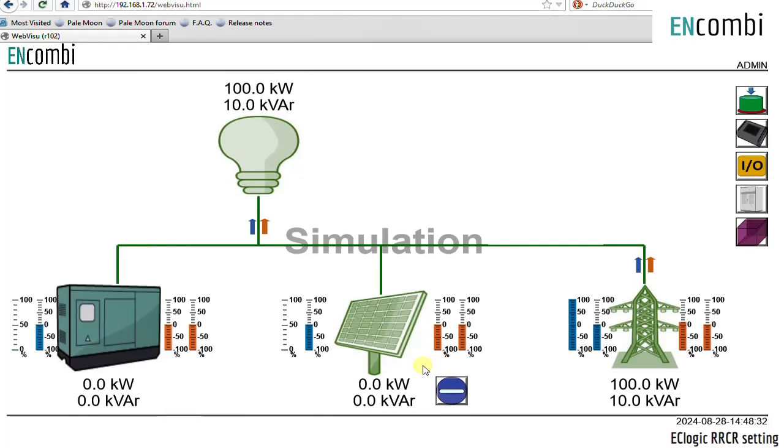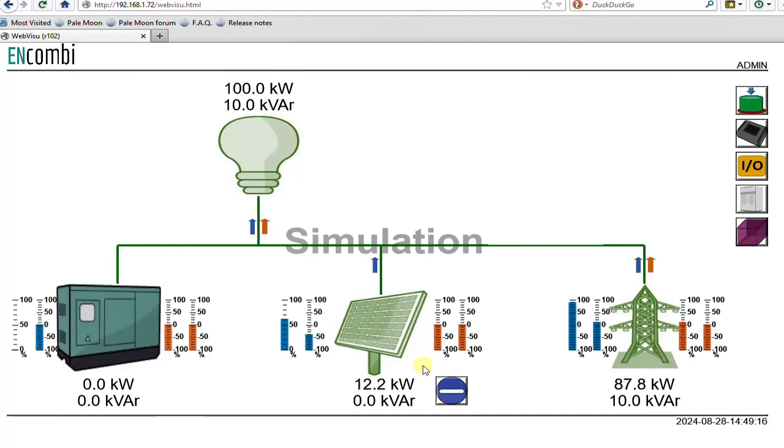Let's manually turn off the input signal again and monitor the PV production reading. Here again you will see the production increasing to the initial level as you observed earlier, which means the input is present and the controller behaves according to the settings.